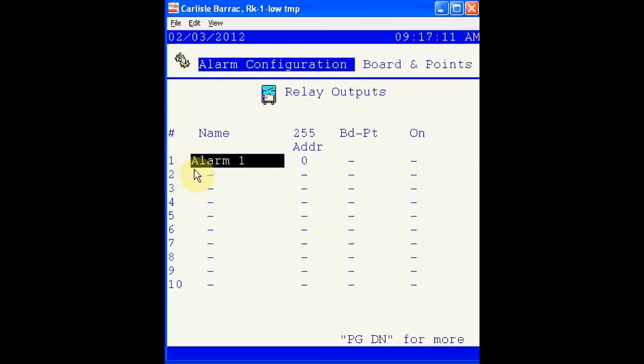Here we see a name was given to the alarm relay called Alarm 1. It's important to note that this alarm relay does not exist on this controller. At this site, Rack 1 is considered unit number 1, but the alarm relay is actually residing on controller 0. So this controller has been set to send its alarms to unit 0 alarm relay, defined as Alarm 1.